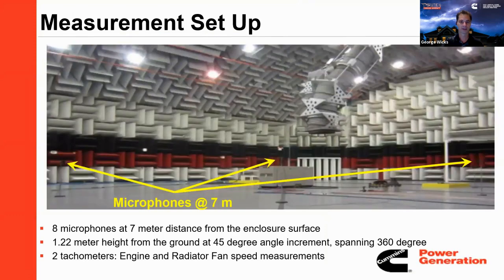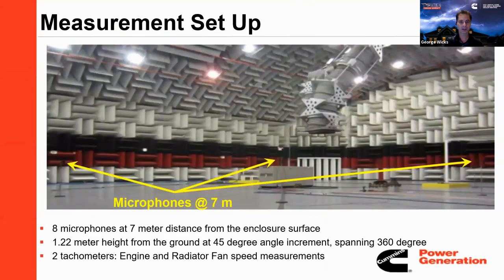There's no reflection and no added noise. There are microphones set up throughout, as I mentioned. That's how serious Cummins and Onan have always been about sound testing. We used to test these units out in the field before this acoustical center was built—you can see a unit there getting tested, with the exhaust pushed out. So we're really only hearing what those microphones pick up from the unit's sound, with no reflections or reverberations bouncing off walls to add noise. That gives us a true, accurate measurement at full load.